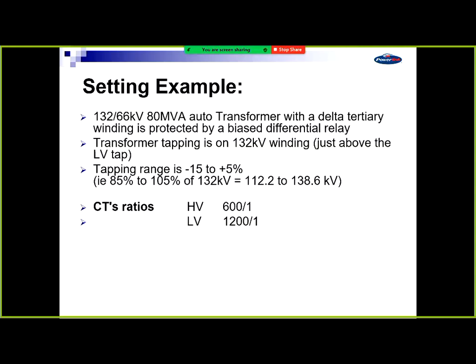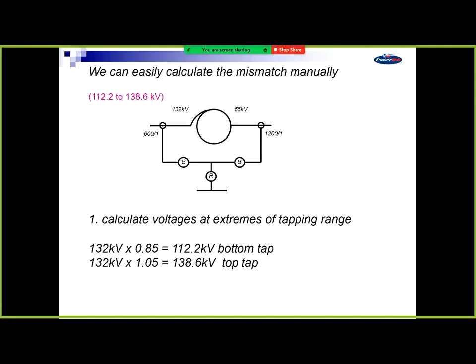80 MVA at 132 kV represents about 380 or 350 amps. So that's why the 600 is there. You also need to check, so that's based on load of the transformer. The other thing to check when you're checking a CT ratio is its transient performance, and you want to look that it doesn't trip on a through fault. And watch the mismatch at the end. So that's our transformer. You then select a tap to look at.